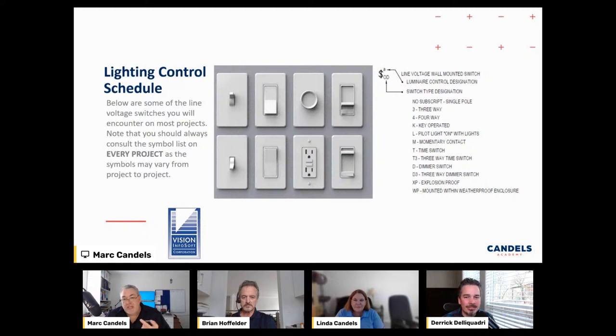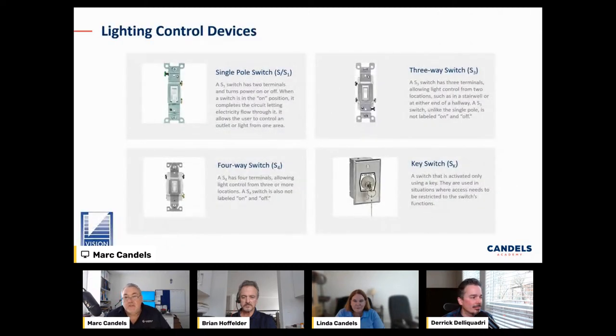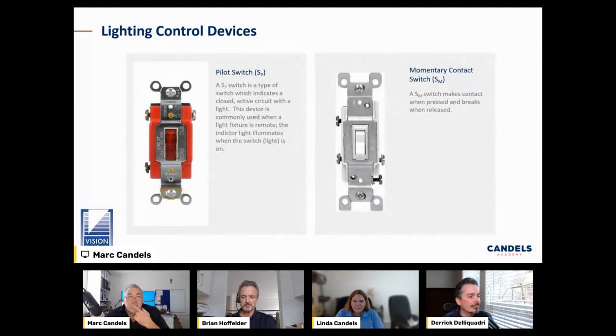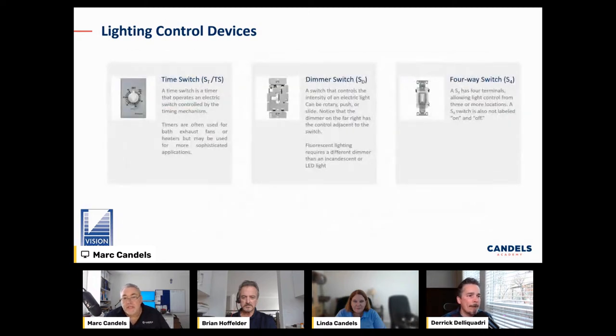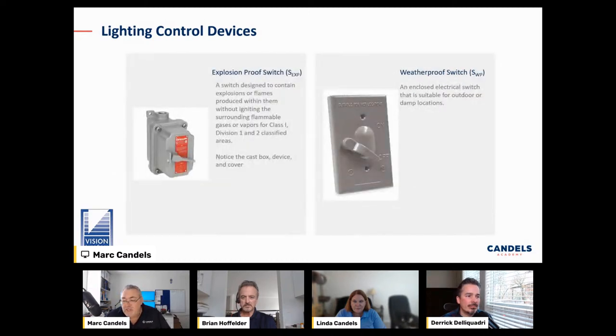Here's a legend from a job that shows all the subscripts. Lighting controls can include single pole switch, three-way switch, key switch, four-way switches, and all appropriate wiring. We have pilot switches — an S with a P. Sometimes you'll see an S with a T, which some think is a toggle or thermal-rated switch. We have an S with an M — that's a momentary contact. Also time switches, dimmer switches, and explosion-proof or weather-proof switches.